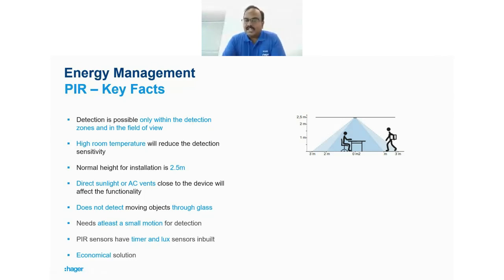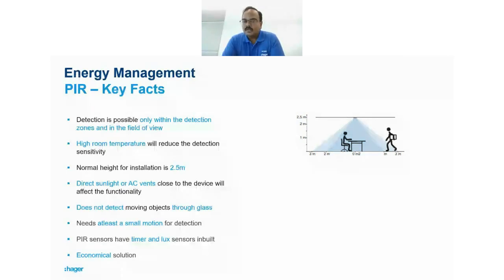Other technologies like ultrasonic, microwave, and hyper frequencies are a little more sensitive than PIRs, but they are much more expensive and have a lot of false triggers — they can see through glass, so someone walking outside the room could trigger the lights inside. Small moving objects like a fan could also cause false triggers. Looking at all this, PIR is actually a very economical and commercially viable solution.